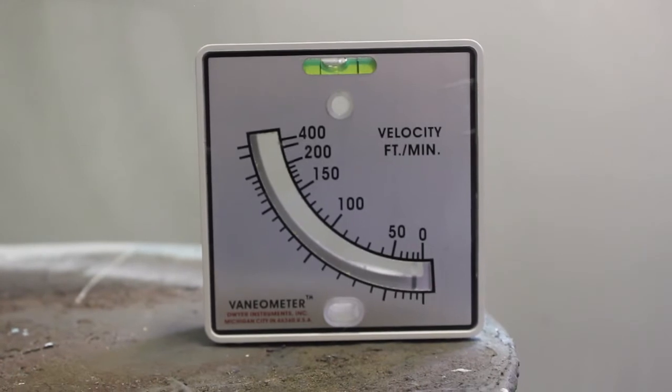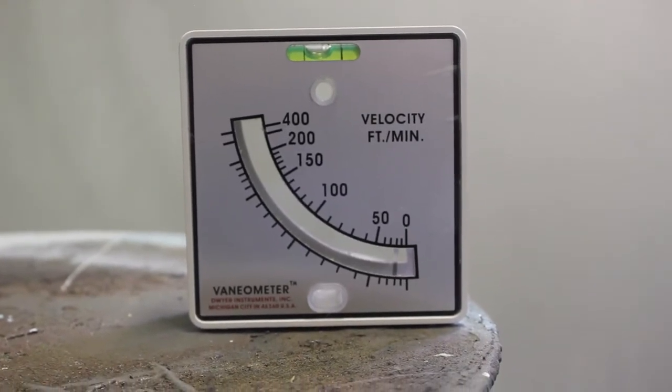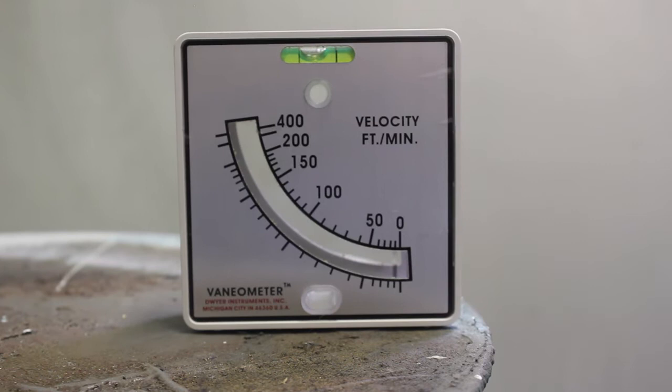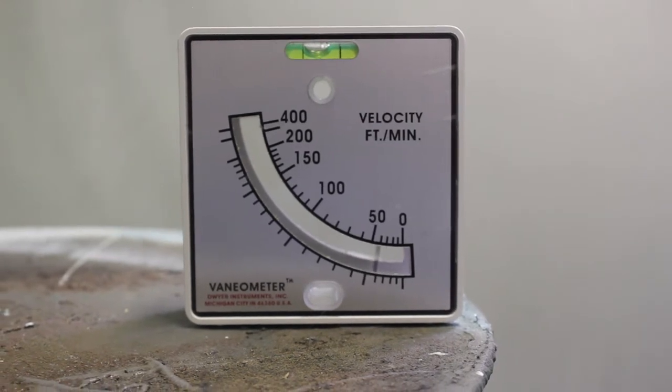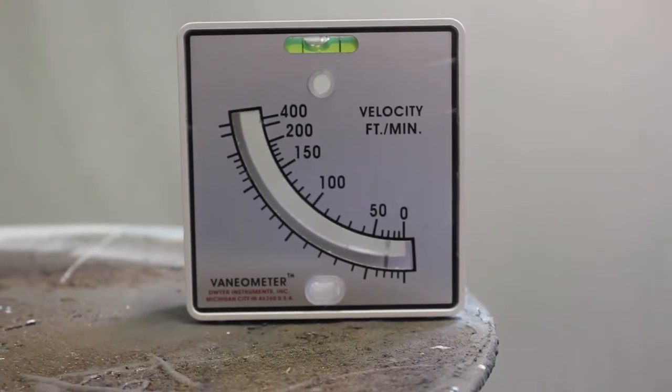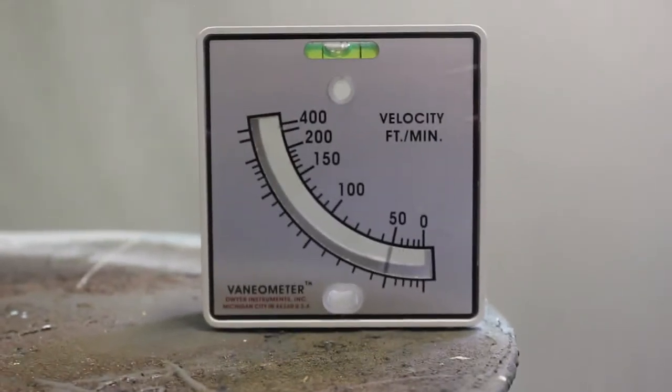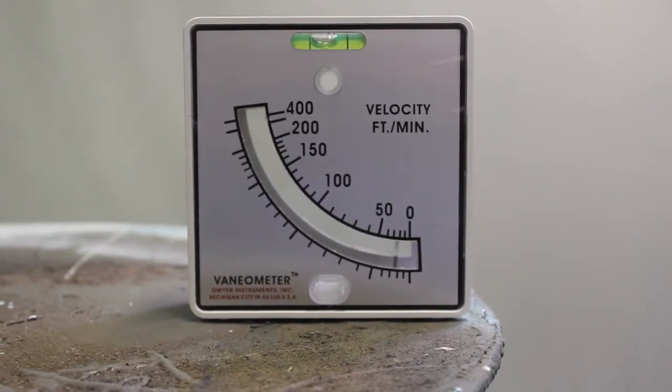Alright, we have the Vaneometer in the paint booth. When you do these measurements, you'll be doing this in a few different areas of the booth to make sure you're getting relatively equal draw across your booth, which in a properly designed booth, the airflow should be relatively consistent in all areas.